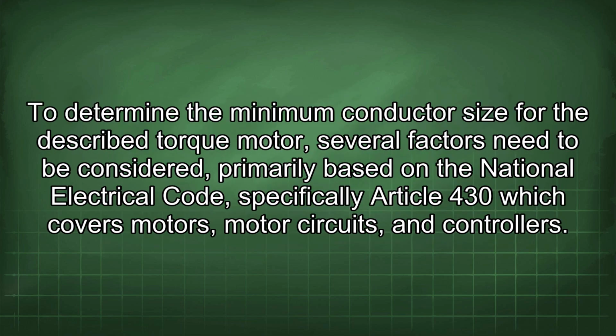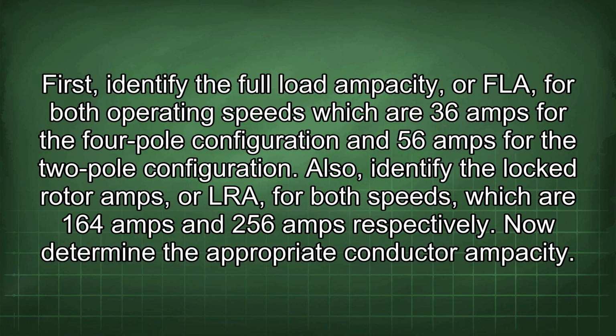To determine the minimum conductor size for the described torque motor, several factors need to be considered, primarily based on the National Electrical Code, specifically Article 430, which covers motors, motor circuits, and controllers. First, identify the full load ampacity, or FLA, for both operating speeds, which are 36 amps for the 4-pole configuration and 56 amps for the 2-pole configuration. Also, identify the locked rotor amps, or LRA, for both speeds, which are 164 amps and 256 amps respectively.